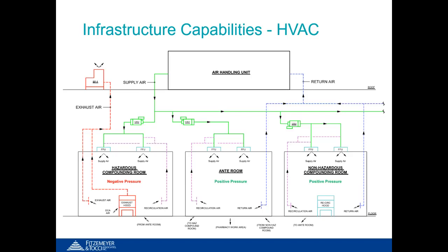A fan filter unit is nothing more than its name implies: a fan, a HEPA filter, and a laminar flow air device. The key to this system's operation is that the fan filter unit's fan provides the additional static pressure required to overcome the pressure drop of the HEPA filter. Additionally, instead of all the return air being recirculated back to the air handling unit, a low return is supplied to the space, which can return air directly back to the fan filter unit. This allows for the equipment to meet the air change requirements. In this system configuration, the air handling unit is only responsible for meeting the cooling, heating, and humidity control needs. The fan filter units supply the HEPA filtered air and meet the air change requirements.